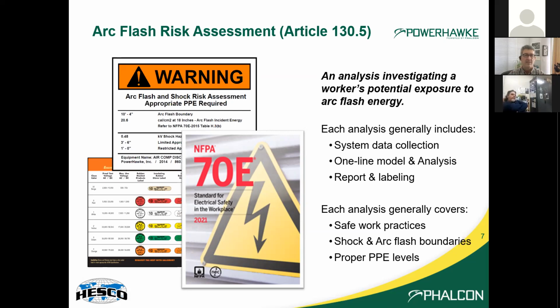Typically, the analysis starts at the utility entrance, where the utility connects to the building, and goes down through the system to the 240 volt or 208 volt levels. We'll talk more about this with the IEEE details, as to how far into the system you really need to go. But you want to go far enough to produce information on arc and shock boundaries and PPE levels that protects your workers. Generally you're not doing arc flash on single phase systems—this is generally a three-phase phenomenon, and single phase is generally not included.